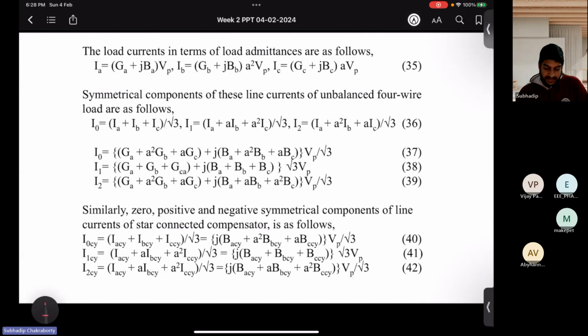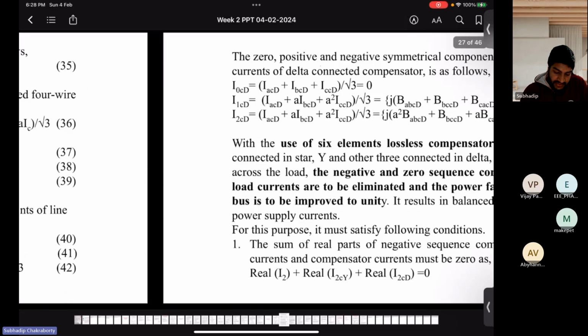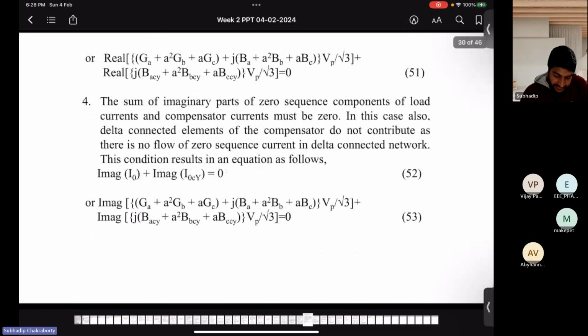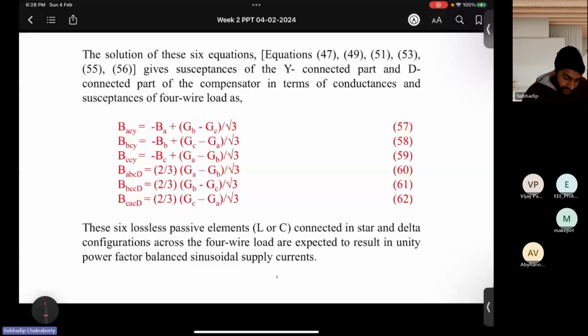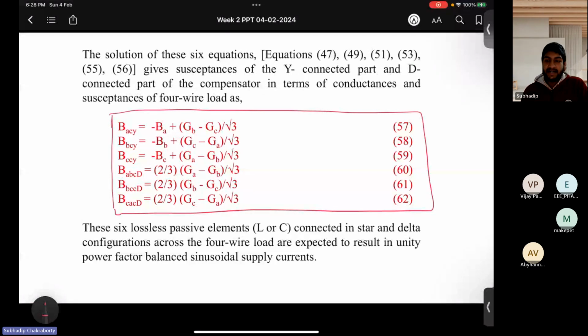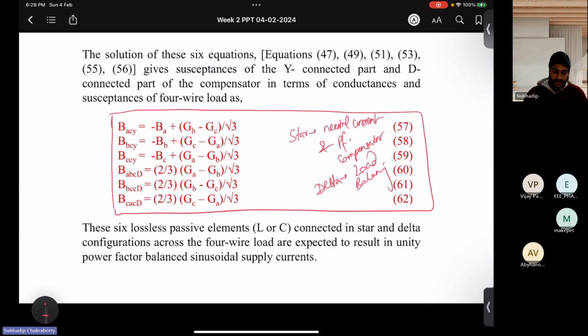Now, if you go through the derivation, you will find these values. So these values are very important. These values are derived keeping the philosophy that the star is acting as the neutral current and power factor compensator. So star, please remember, star: neutral current and power factor compensator, and delta, what is it doing? Load balancing. That is, the negative sequence components. So if this is the philosophy, then the values are like this.